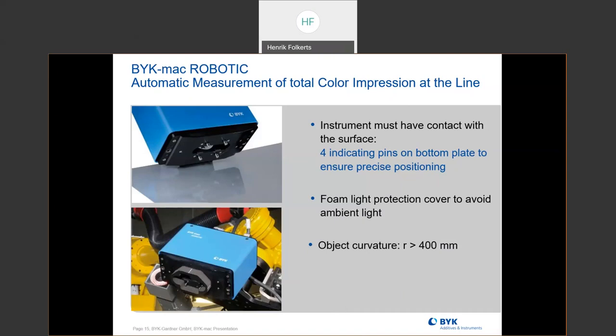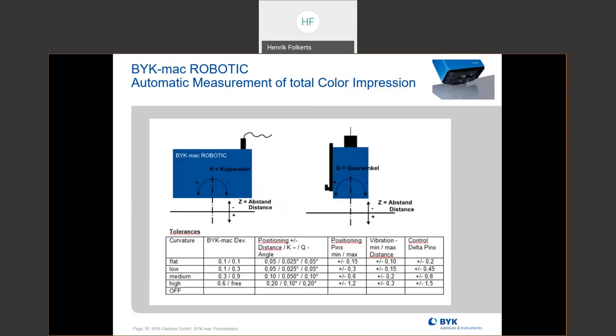For the curvature of the BYK-mac, the radius has to be less than 400 millimeters. The pins work the same as the handheld — you have flat, low, medium, and high settings. For the robotic, we do not use the pin setting of off because the pins have to engage at some level in order to make sure the measurement is completed. If we turn the pins off, the instrument would not know it's in the proper position and so it would not measure.